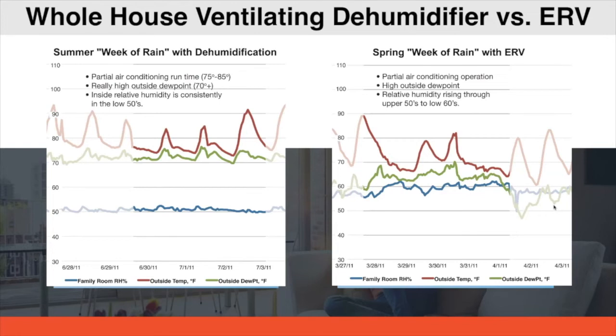The blue line there is the relative humidity in the living space. The red line is the outdoor temperature, and the green line is the outside dew point. And basically, by using that ERV, it was following the dew points outside. It was bringing in moisture, again, less moisture than using a different ventilation strategy, but it was still bringing in moisture to the space.